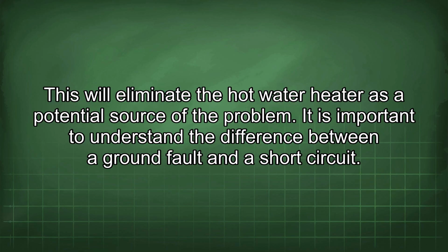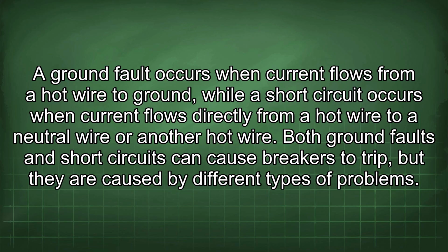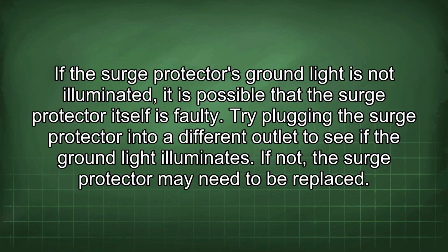This will eliminate the hot water heater as a potential source of the problem. It is important to understand the difference between a ground fault and a short circuit. A ground fault occurs when current flows from a hot wire to ground, while a short circuit occurs when current flows directly from a hot wire to a neutral wire or another hot wire. Both ground faults and short circuits can cause breakers to trip, but they are caused by different types of problems. If the surge protector's ground light is not illuminated, it is possible that the surge protector itself is faulty. Try plugging the surge protector into a different outlet to see if the ground light illuminates. If not, the surge protector may need to be replaced.